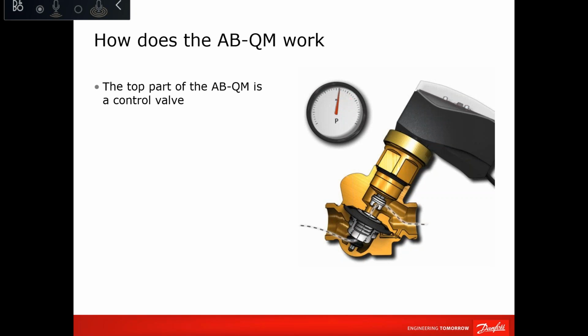For sizes DN40 and bigger, you also have a stainless steel pressure controller cone. The two-way part cones are brass. This is up to DN100. For DN125 and bigger, everything inside the valve is stainless steel, except the membrane of the pressure controller, which has to be EPDM. So we have either stainless steel or brass, dezincification-resistant brass. So it's only metallic internal material. We don't have plastic. I hope that answers the question.